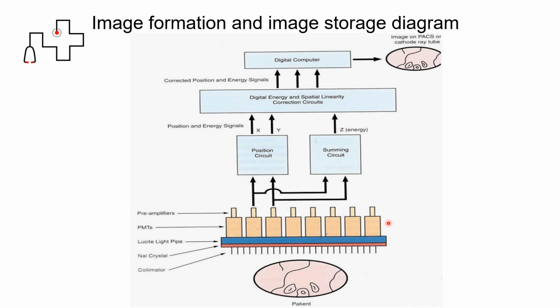So the scintillation crystal commonly used in gamma cameras is made from sodium iodide with trace quantities of thallium added to increase light production. This crystal composition is effective for stopping most common gamma rays emitted from the radiopharmaceuticals used in nuclear medicine.